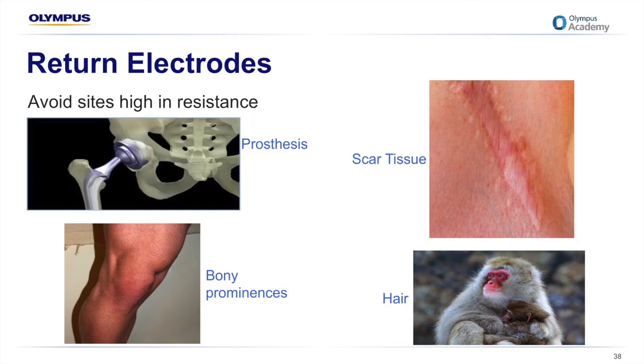There must be adequate tissue perfusion to promote electrical conductivity and to dissipate heat. Ideal placement for return electrode plates is over a clean, dry, large muscle mass. Other sites may increase resistance to current flow, thereby increasing the risk of burns. Avoid excess fatty tissue, bony prominences, scar tissue, and any known metal prostheses. Place the dispersive electrode as close to the surgical site as possible in order to allow the current to exit the body as quickly as possible.